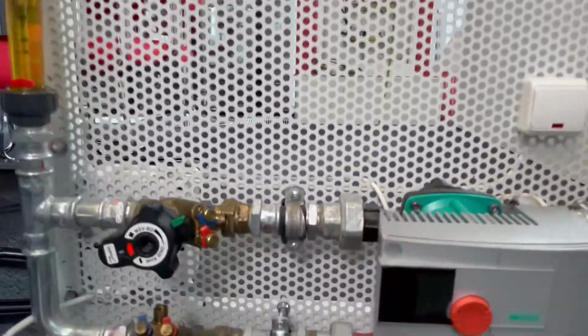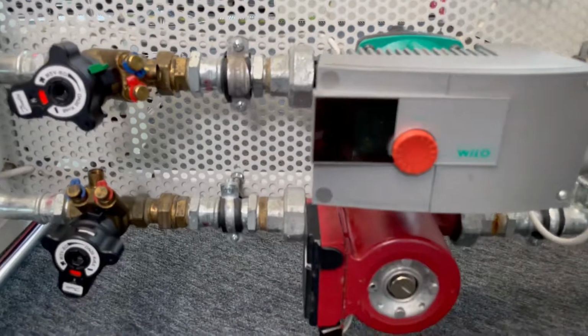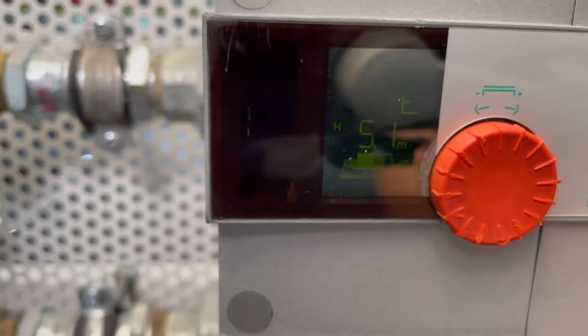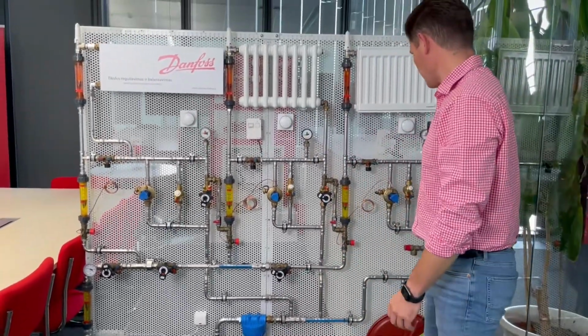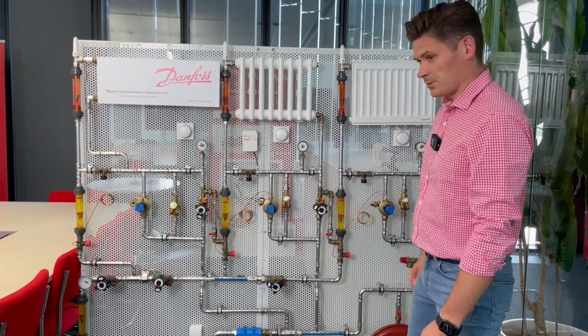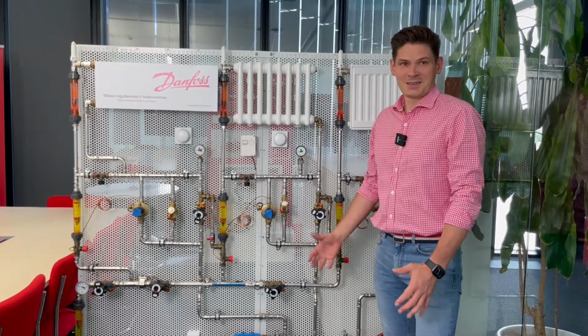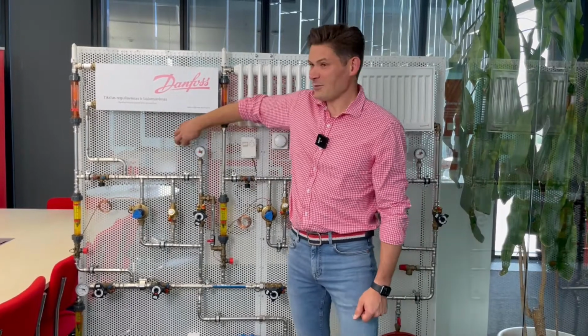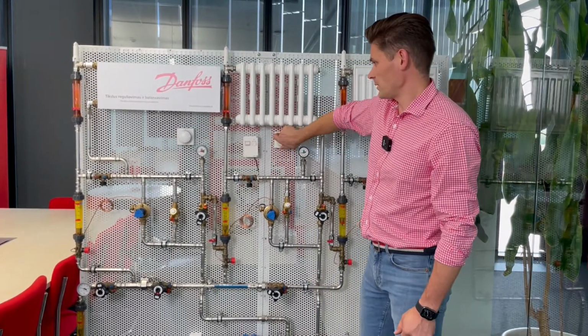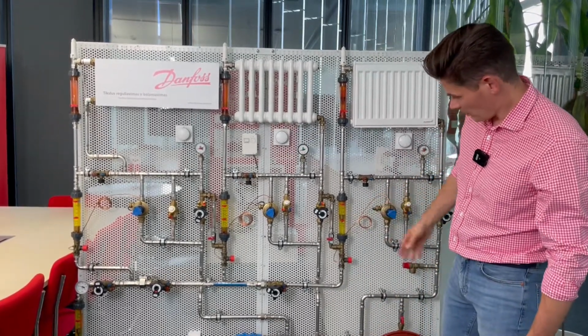Let's check the settings of the circulation pump. What does it show in its window, on its screen? Okay, it shows something like 5.1 meters of water. It is 51 kilopascal. Okay, time to try to close something. Here the sun comes again, and the thermostats close to 30%, 60%, 50%. Let's take a look at the last riser.